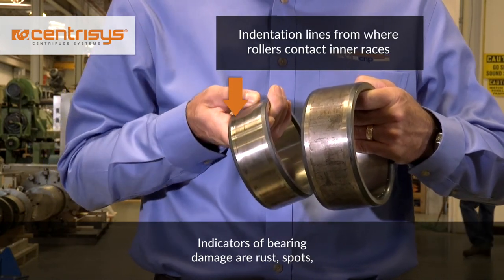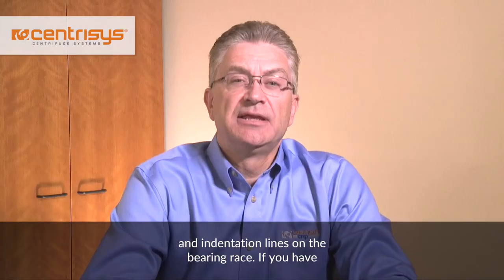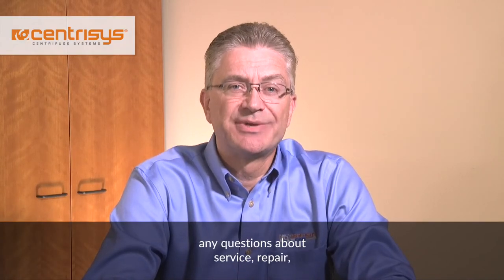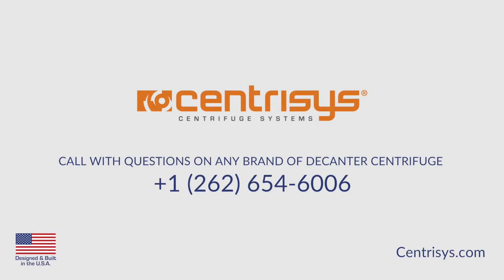Indicators of bearing damage are rust spots and indentation lines on the bearing race. If you have any questions about service, repair, or maintenance on any brand of decanter centrifuge, please give us a call at Centrisys: 262-654-6006.